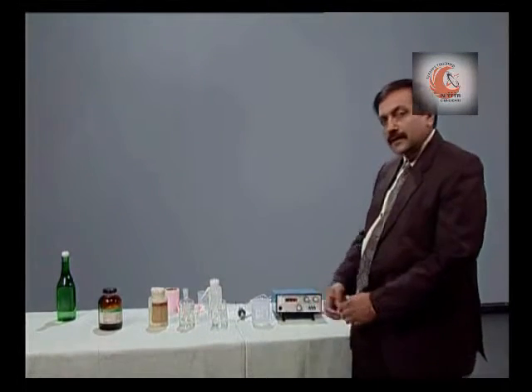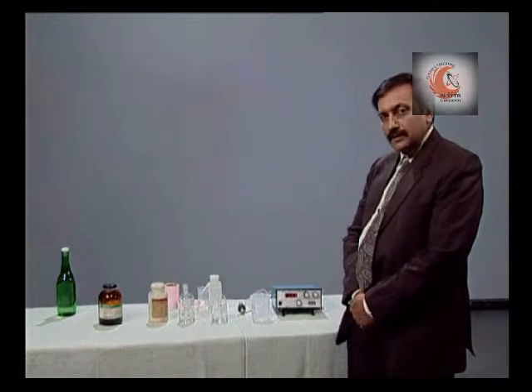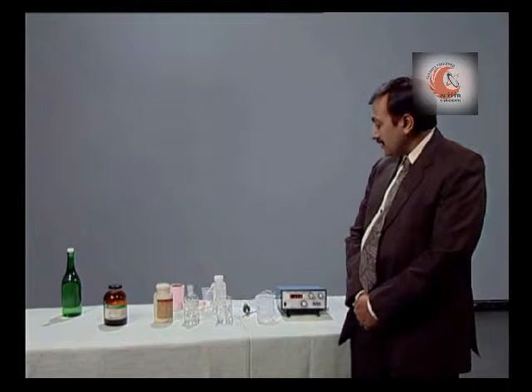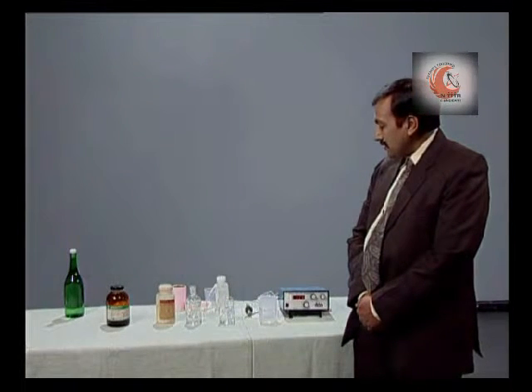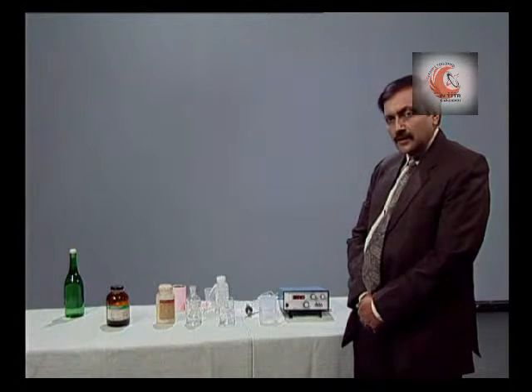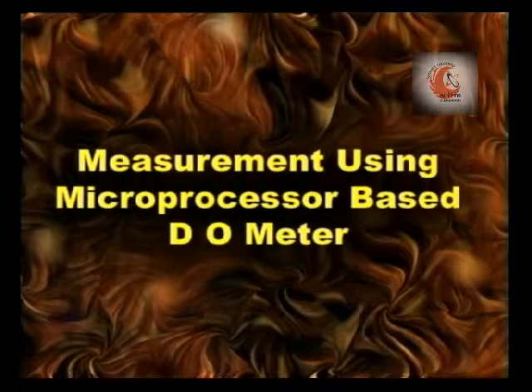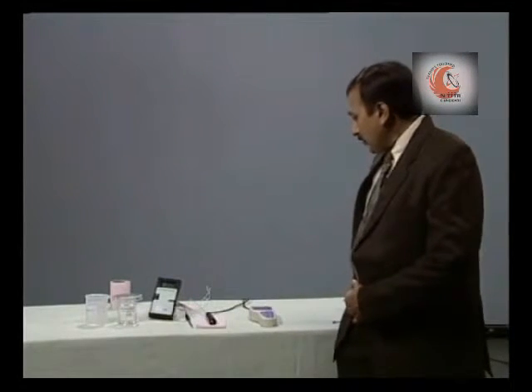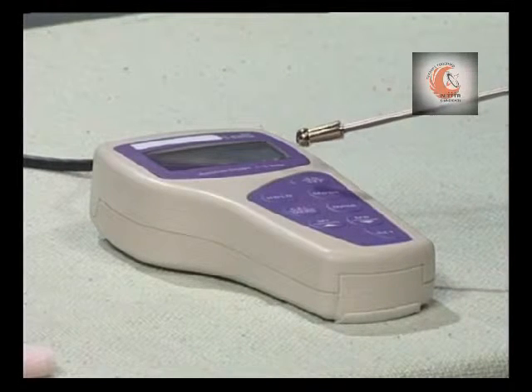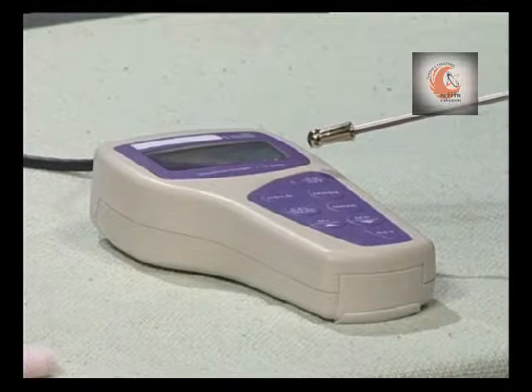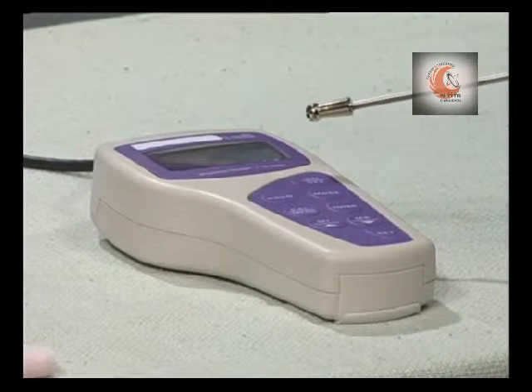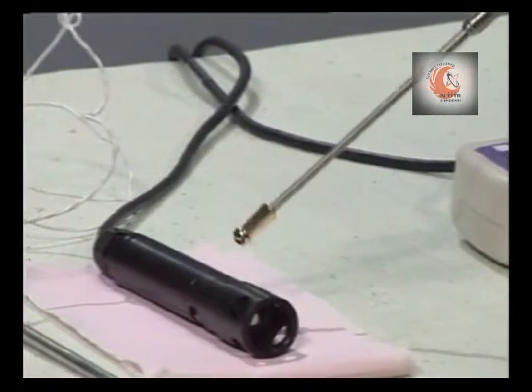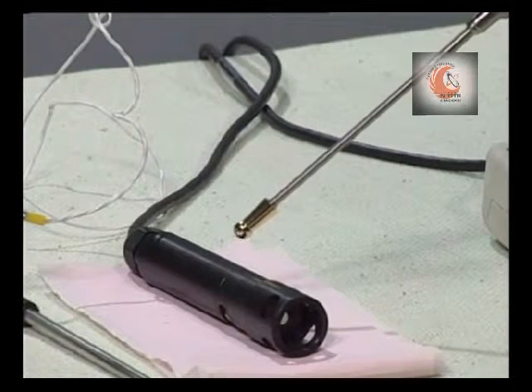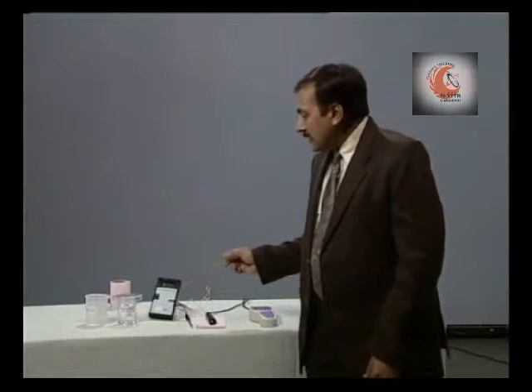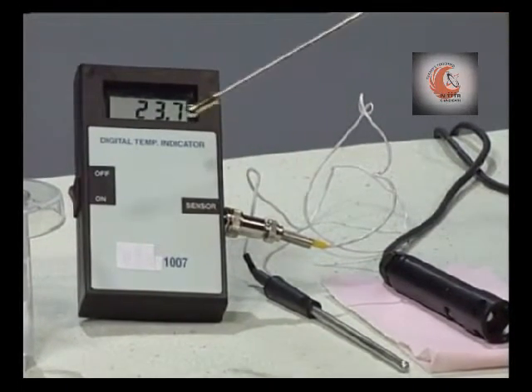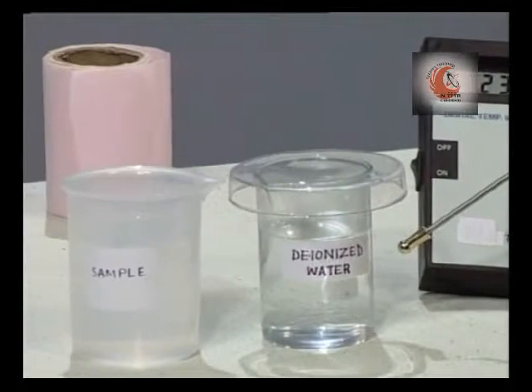Now, what you have just seen is a laboratory method of measurement. There are more advanced methods which are available. These instruments are microprocessor based. This is one such instrument which is microprocessor based. It is highly compact and very accurate. It comes with a compatible DO electrode or DO probe. You also would require a temperature indicator and deionized water for measurements.